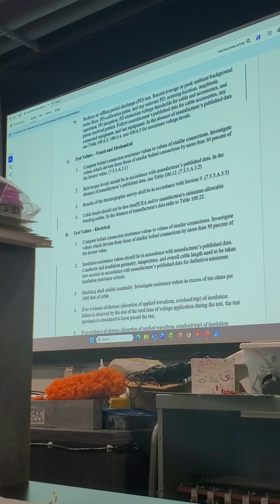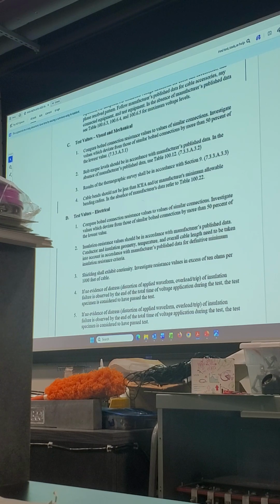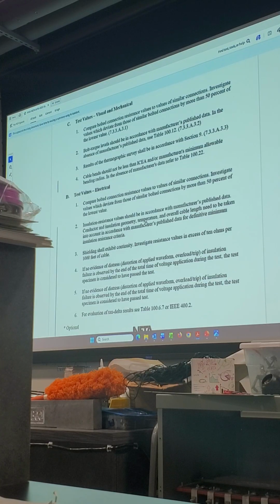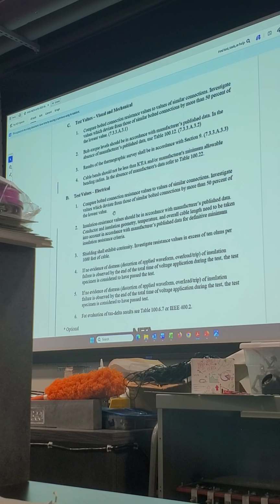All right, cool. So by the time we get to evaluating our test values here, we take the DLRO and go across A, B, C, or whatever it may be. Compare bolted connection resistance values to values of similar connections. Investigate values which deviate from those of similar bolted connections by more than 50% of the lowest value.